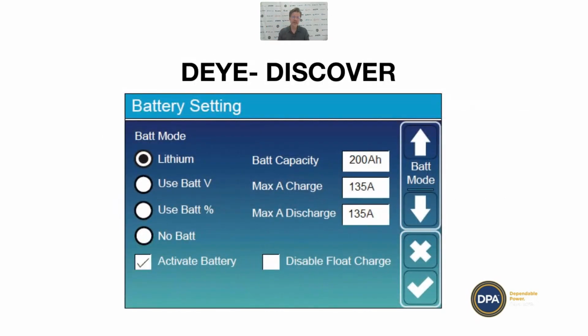So when we're setting up our settings for closed loop with Deye, we're going to go into the battery settings and click on lithium. You can set the battery capacity here, but it doesn't really matter because it's getting the state of charge information from the battery. Set your charge current. Obviously, a lot of the time it's going to be lower than the maximum the battery can handle anyway, depending on what size inverter you're using. And you shouldn't really have a larger inverter that's capable of putting more than that in, because usually that would be a bad design, but there might be some scenarios when you do that.